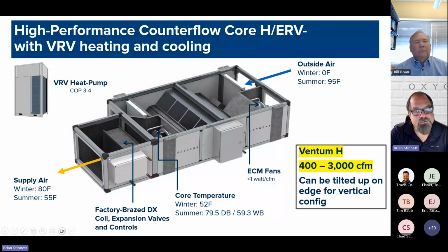Here's another example. This one actually is the energy recovery unit. This is our counterflow Ventum ceiling hung unit, 18 inches tall, up to 1,000 CFM. And here you can see it's got a VRV heat pump system with a VRV heating and cooling coil. We do a lot of VRV heat pump heating and cooling projects in cold climates because you can provide way more than enough heat with that VRV outdoor unit.